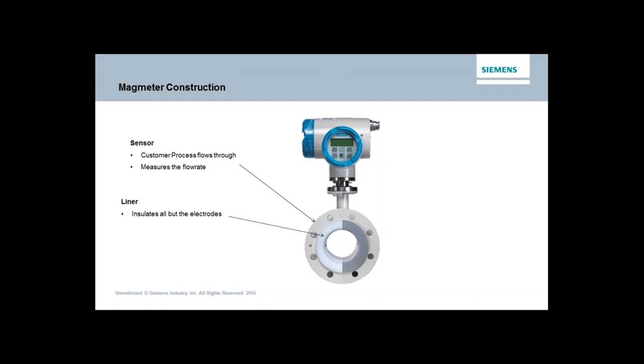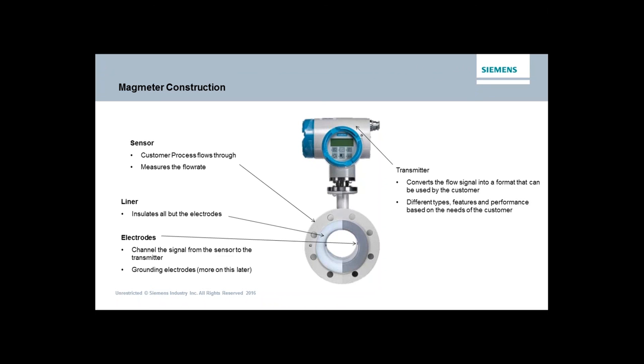Staying with the electrodes for just a moment — you may find in some mag meter designs some electrodes mounted along the bottom of the pipe in a horizontal installation. That would be a grounding electrode, and the purpose is to provide a way to grab any stray voltages that may be part of the process, coming down the process line or building up from static electricity, and getting rid of those so that the only thing being measured by the device is the voltage being created by the magnetic field and the conductive liquid.